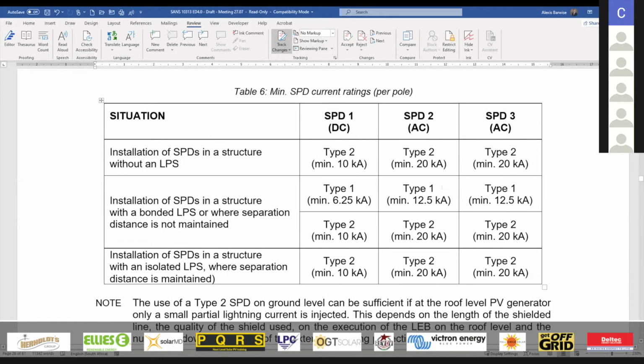Here you can see a very nice table. It shows us that if we are installing SPDs in a structure without any lightning protection—not even considering external lightning protection, a perfect example being a home application—then SPD 1 on the DC side would only need to be a type 2, minimum 10 kA. SPD 2 would also be type 2, since we're not dealing with lightning currents, with a minimum of 20 kA because it's an AC arrestor. And SPD 3 would be the same.